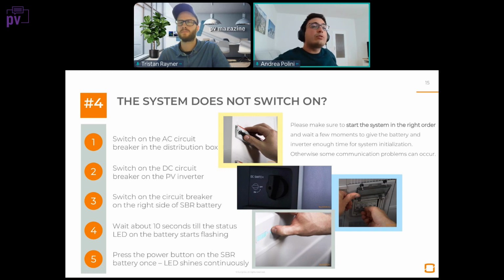You can try to turn on first the AC, so the AC grid is arriving at the inverter, then the DC, so turn on the PV, and then switch on the circuit breaker on the right side of the SBR battery, and then wait 10 seconds. For models of the SPR that still include the button, press the button. But for models that don't include it, like the newer models we have now on the market, where it's just an LED indicator, there is no need to press the button anymore.